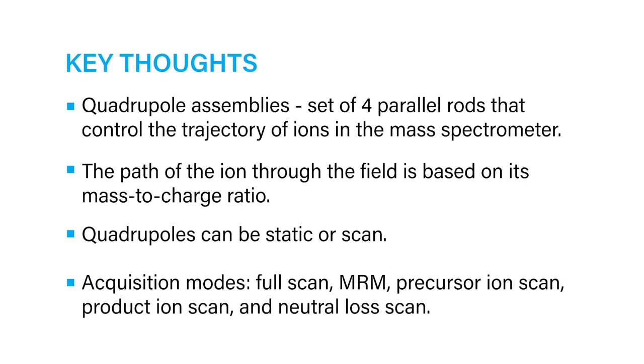And lastly, they can also scan where the RF and DC voltage settings are ramped to let ions through the quadrupole in order of increasing mass-to-charge ratio. A wide range of acquisition modes such as full scan, MRM, precursor ion scan, product ion scan, and neutral loss scan are available on tandem quad mass spectrometers.